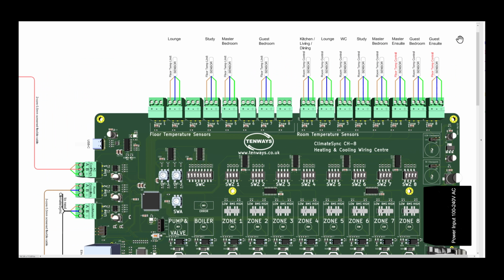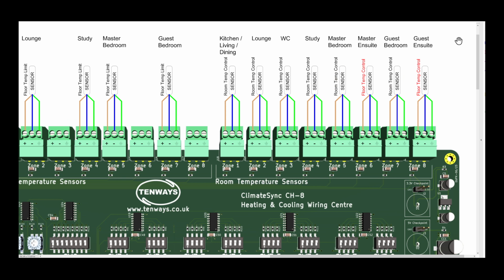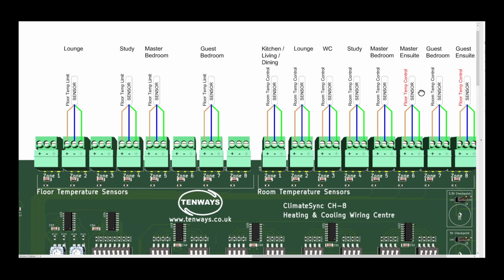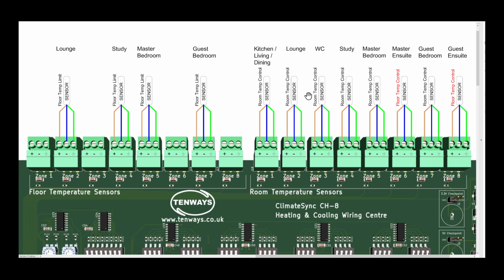So let's enlarge a bit the sensor area and discuss the sensors. Here we go. So now we can see all sensors, 16 sensors, sensor options. In this wiring center, as we can see, we have all 8 zones active. We have floor temperature sensors, and some of the rooms, normally this will be rooms with timber flooring, where floor temperature limit is required, and you can set what will be the floor limit temperature on the controller, but that will be the setup video.